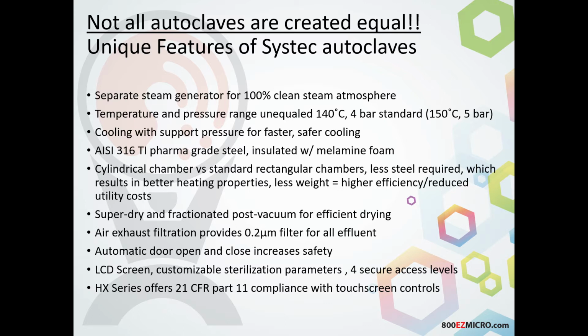Additionally, that's twice the amount of steel that we're going to need to heat up and cool down each and every cycle. With the Systec Autoclaves being a cylindrical chamber versus a standard rectangular chamber that would have that jacket, we have better heating properties, we have less weight, so we don't have to worry as much, especially if you're ordering a larger type system. You don't have to look at infrastructure as much as you would for the flooring in order to hold the system.